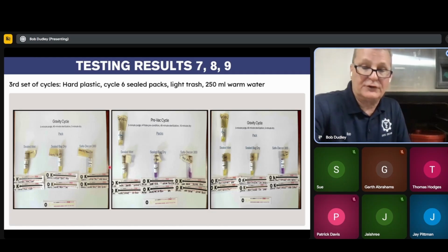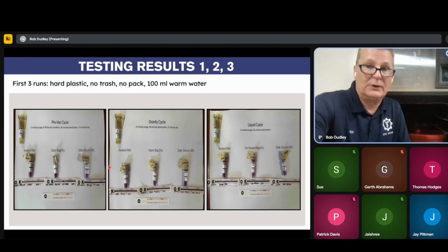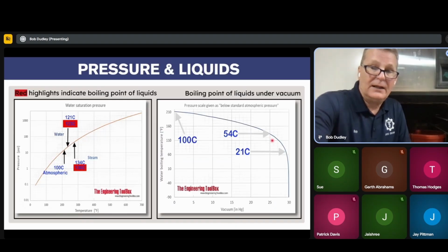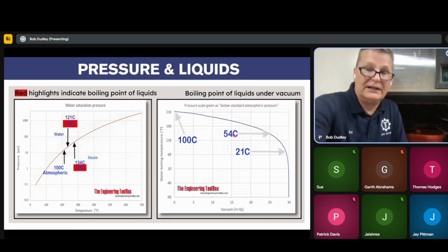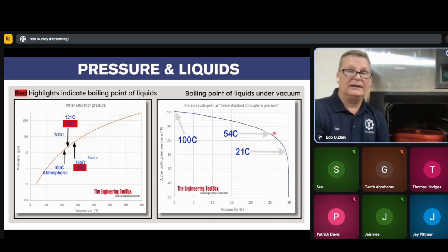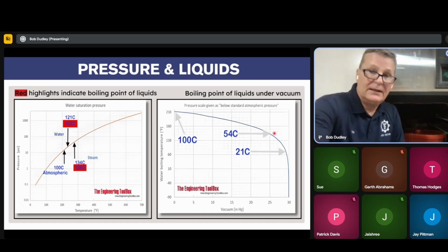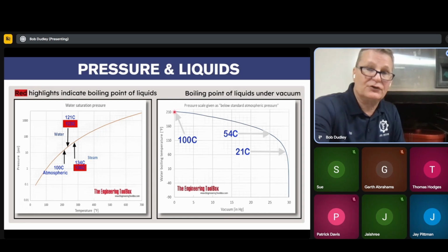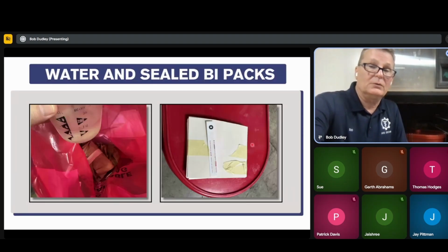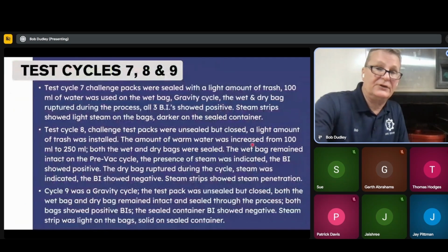And also, I'm going to go back, because this is something critical. I want to go back here real quick. I forgot to explain this to you. When you see this 54, and this is the boiling point, I want you to understand why steam doesn't kill. With steam under a vacuum, your steam temperature is 54 degrees, just so you know. Here, just because it produces steam, your steam temperature is 69 degrees. So when it gets to atmospheric and turns to steam, it's not 212. As you pull vacuum, it gets less and less. Depending on where you are in the country, you will see that that's why steam doesn't do it. That's why you need that heat.